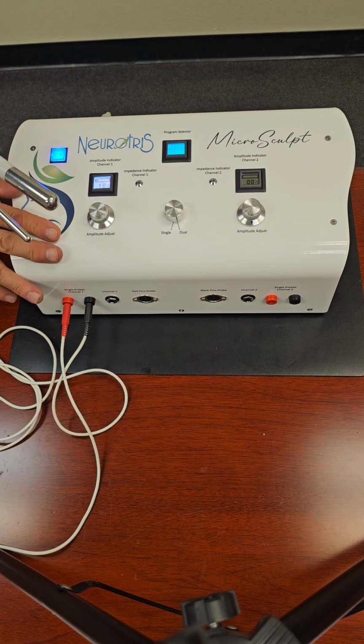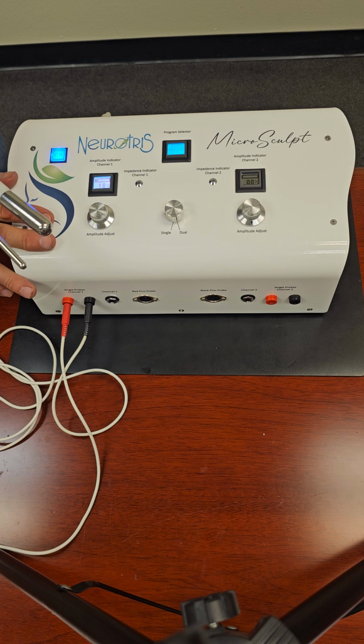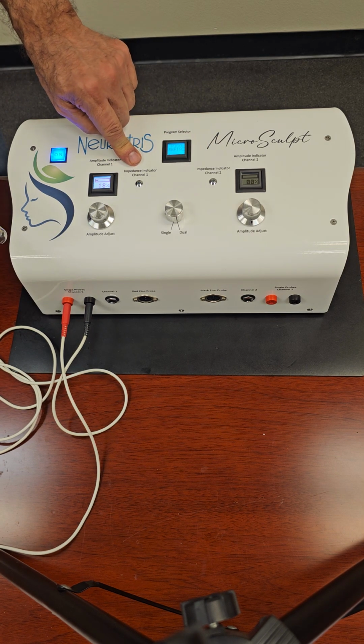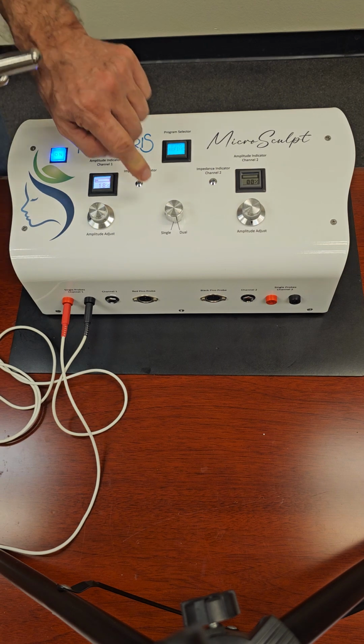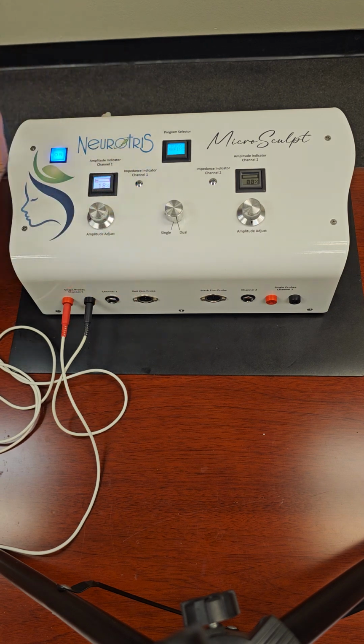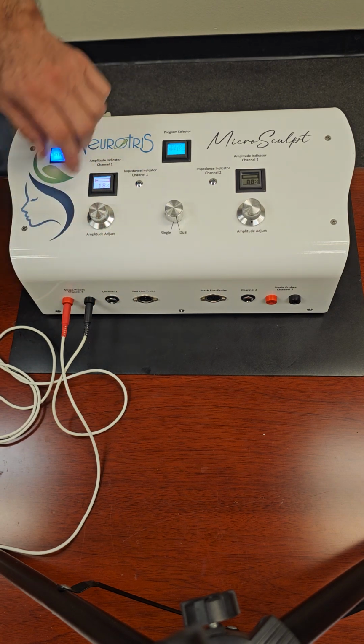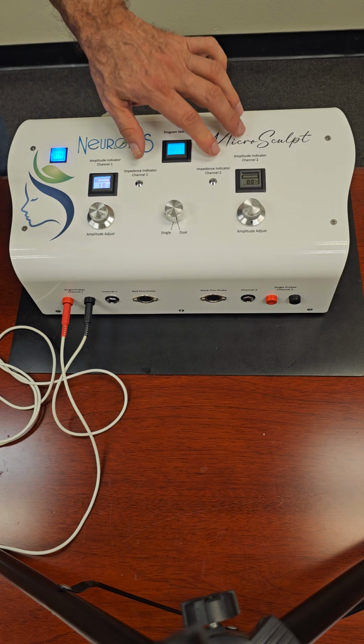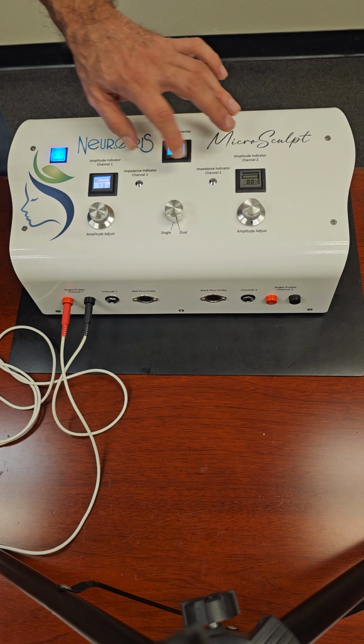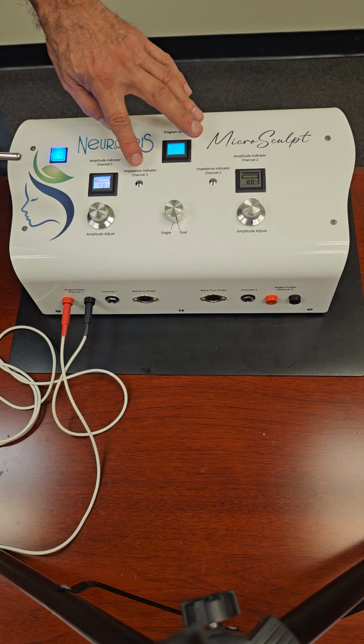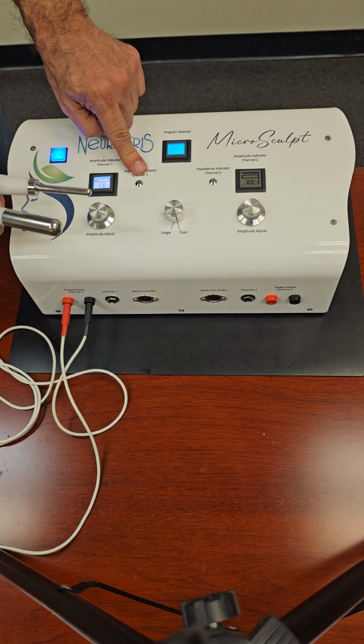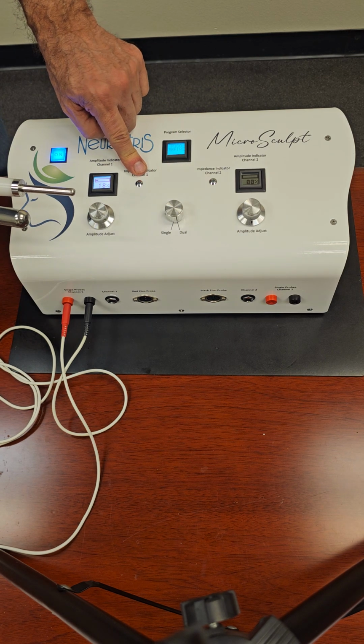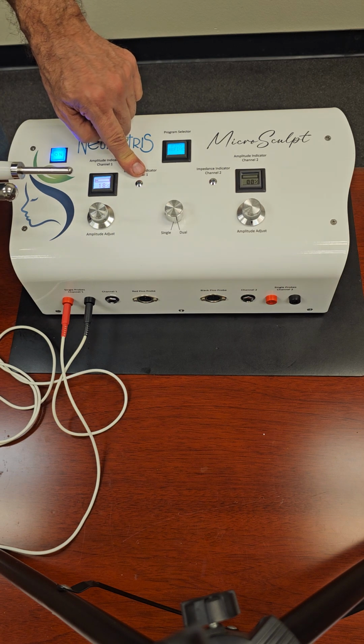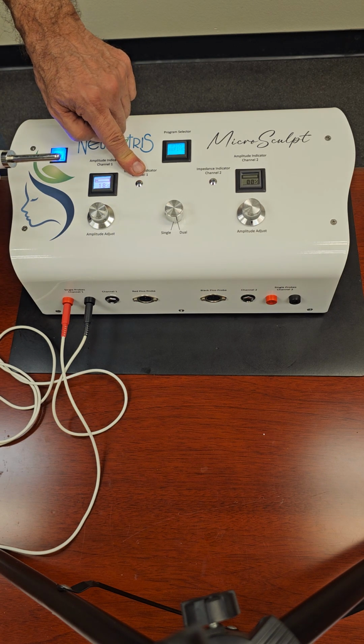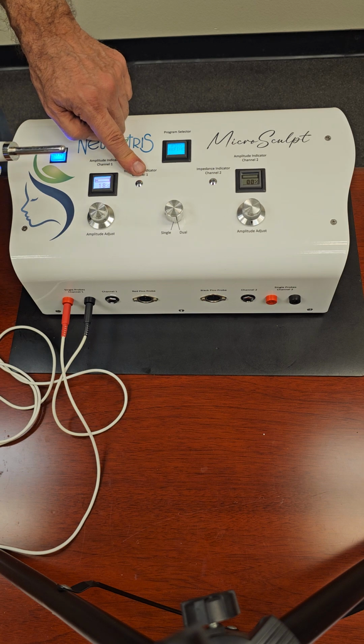Well, what's a very good feature about this machine is it has a skin impedance computer built into the system. So what that means is each of your clients have different skin types, right? So depending on their skin density, the machine is going to automatically sense that and make sure that you're outputting the right level. So we have these impedance lights on this new machine. So when you touch the probes onto the face, they will come on when the impedance is correct, and that means it's at a good level.